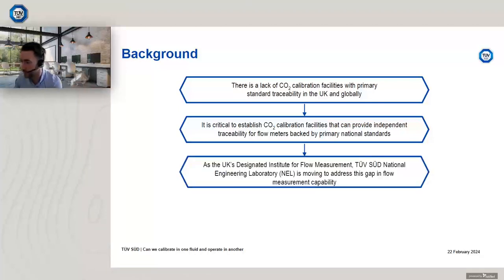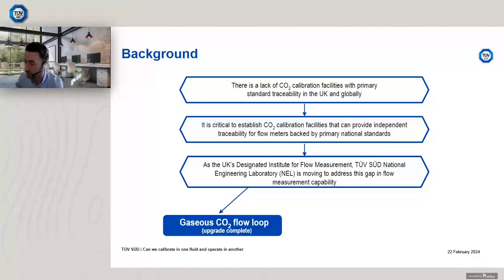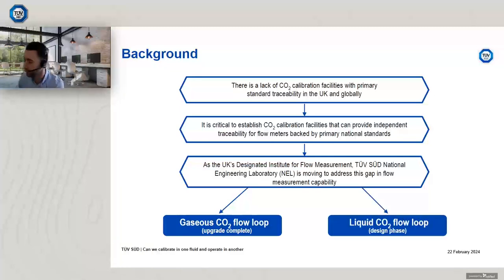So as the UK's Designated Institute for Flow Measurement, TÜV-SÜD, also known as NEL from the National Engineering Laboratory, we're moving to address this gap in two ways. Two fluids. So the gaseous CO2 flow loop that I've just mentioned, and that upgrade's been complete, and we're looking to bring full traceability in-house for that in future. And then to a liquid CO2 flow loop. So this is what I'm involved in just now. I'm working with the design of the liquid CO2 flow loop. We have some funding to build a relatively small scale, so nominal 2-inch facility with a primary, I should add, for liquid dense and supercritical CO2.